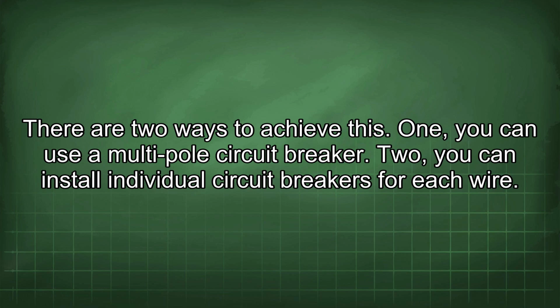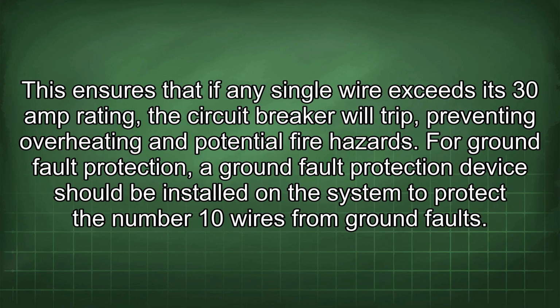There are 2 ways to achieve this. 1. You can use a multi-pole circuit breaker. 2. You can install individual circuit breakers for each wire. This ensures that if any single wire exceeds its 30 amp rating, the circuit breaker will trip, preventing overheating and potential fire hazards. For ground fault protection, a ground fault protection device should be installed on the system to protect the number 10 wires from ground faults.